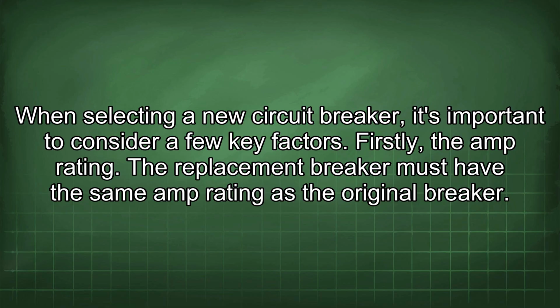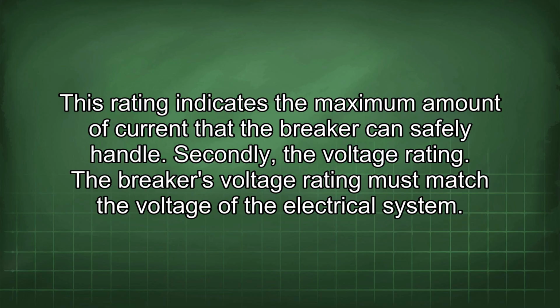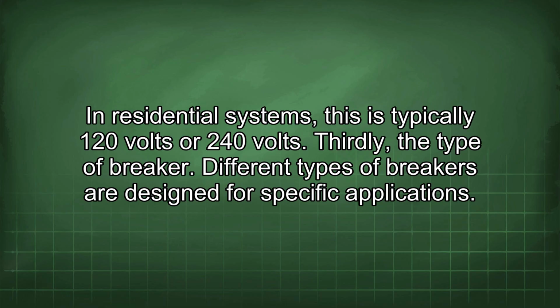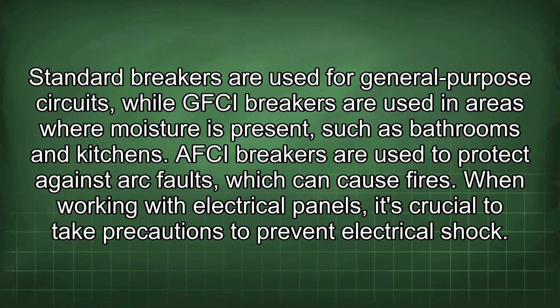When selecting a new circuit breaker, it's important to consider a few key factors. Firstly, the amp rating. The replacement breaker must have the same amp rating as the original breaker. This rating indicates the maximum amount of current that the breaker can safely handle. Secondly, the voltage rating. The breaker's voltage rating must match the voltage of the electrical system. In residential systems, this is typically 120 volts or 240 volts. Thirdly, the type of breaker. Different types of breakers are designed for specific applications. Standard breakers are used for general-purpose circuits, while GFCI breakers are used in areas where moisture is present, such as bathrooms and kitchens.